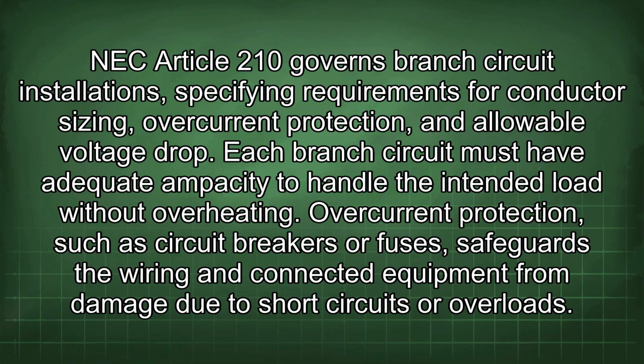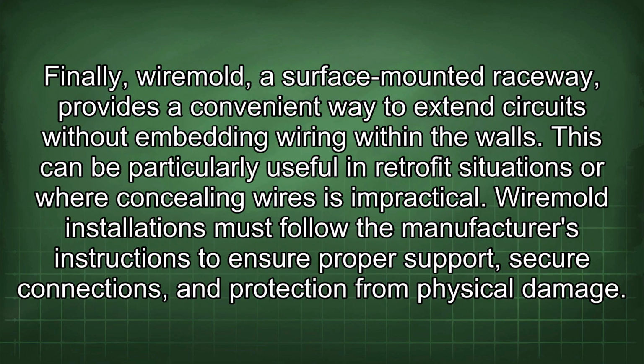Overcurrent protection, such as circuit breakers or fuses, safeguards the wiring and connected equipment from damage due to short circuits or overloads. Finally, wiremold, a surface-mounted raceway, provides a convenient way to extend circuits without embedding wiring within the walls. This can be particularly useful in retrofit situations or where concealing wires is impractical. Wiremold installations must follow the manufacturer's instructions to ensure proper support, secure connections, and protection from physical damage.